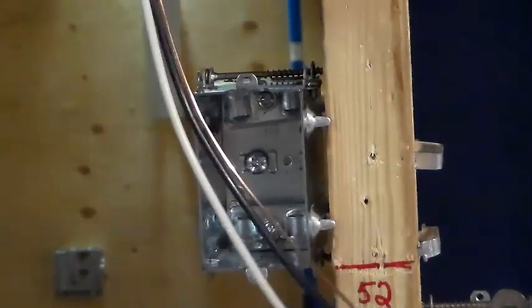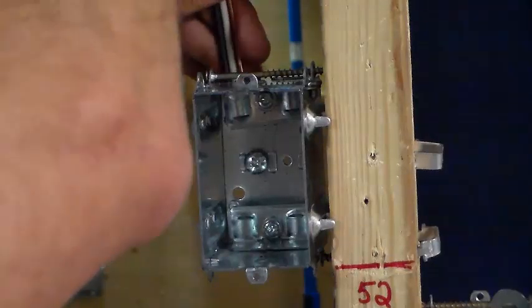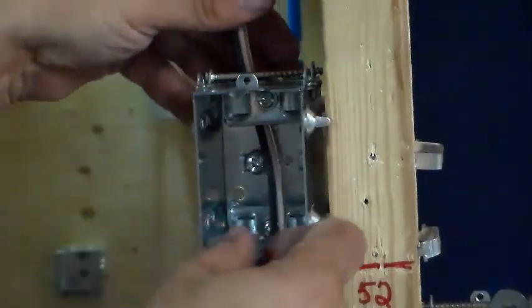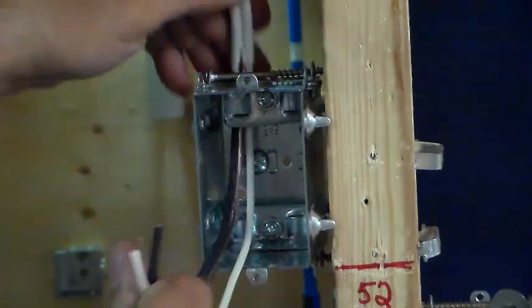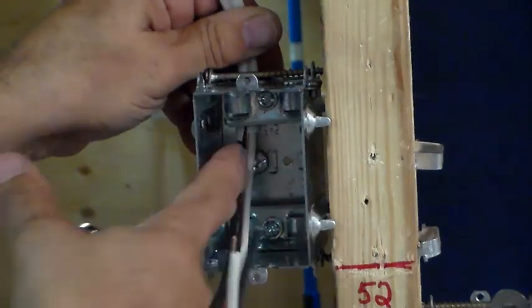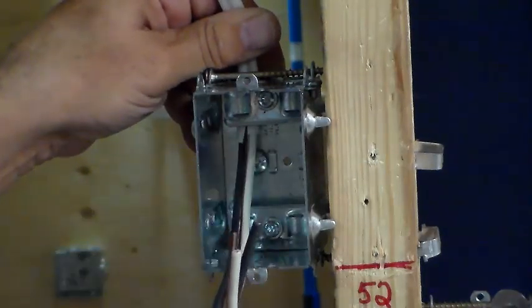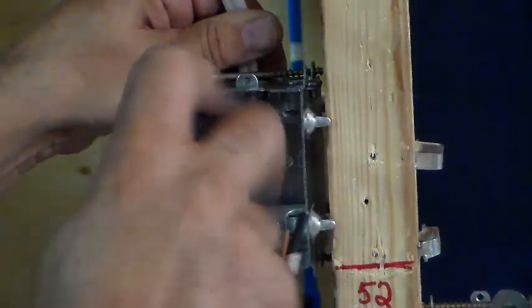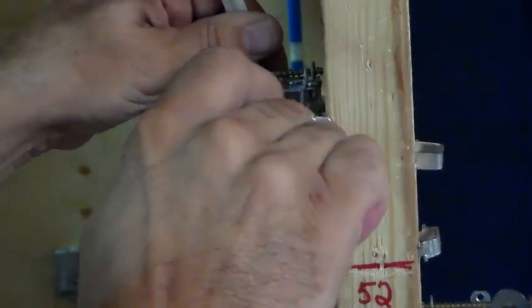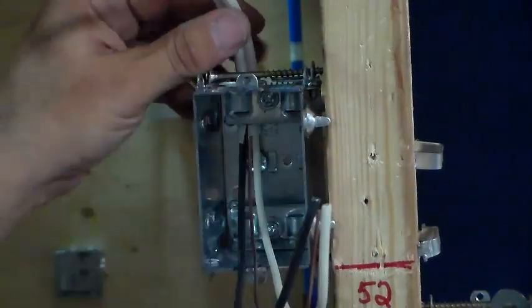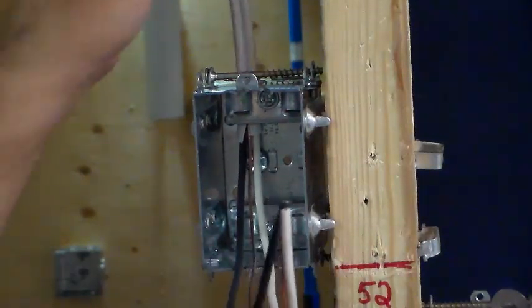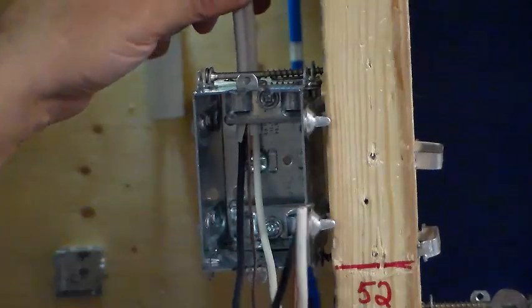Okay, we're zoomed into the box. So I'm going to take my cable now and I'm going to put it into the back of one of the holes. And bring the cable forward. I put a little bit of curve through it so when I push it in it comes forward and doesn't get caught in the back. And I want the cable to the point where I can just see the white in the back. You want to see the sheath on it. And then you tighten the clamp on the screws. Not too tight, just snug enough so that the wire when you tug on it doesn't come loose. It still stays in the box. So that's what we're looking for is for the cable not to move or be able to pull it out.